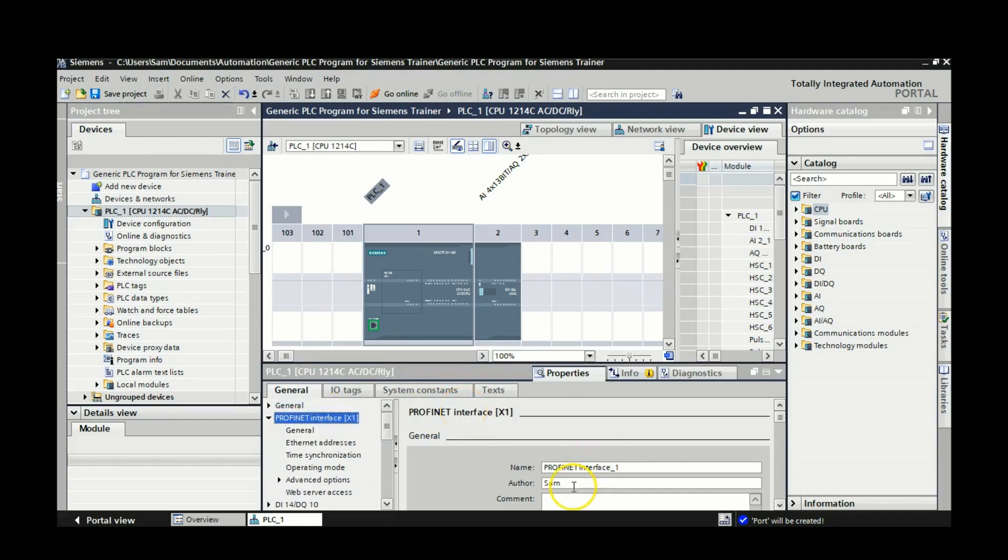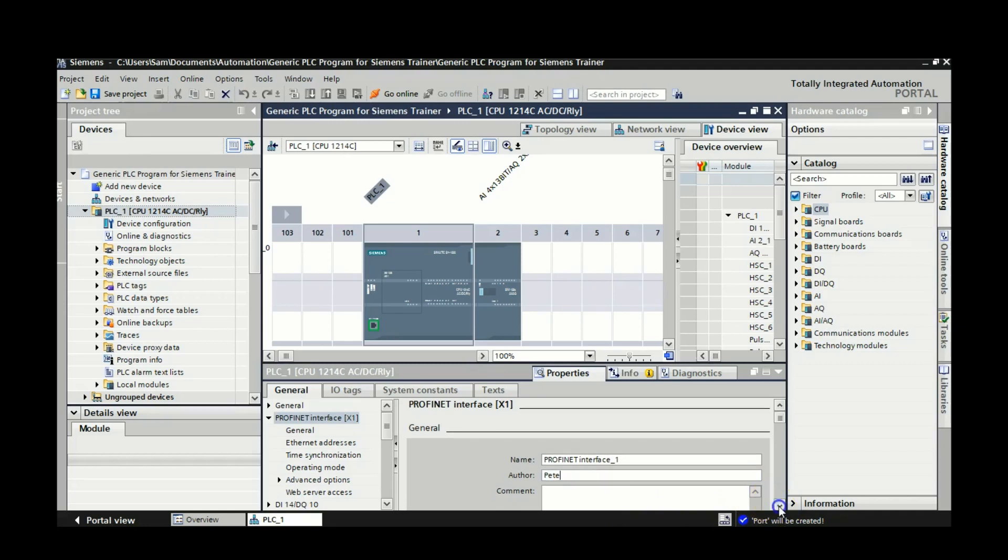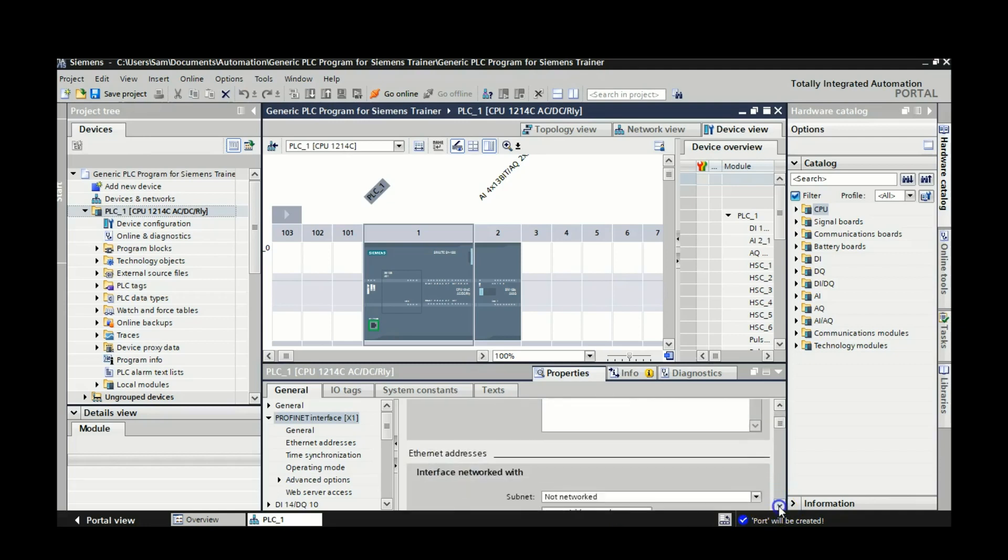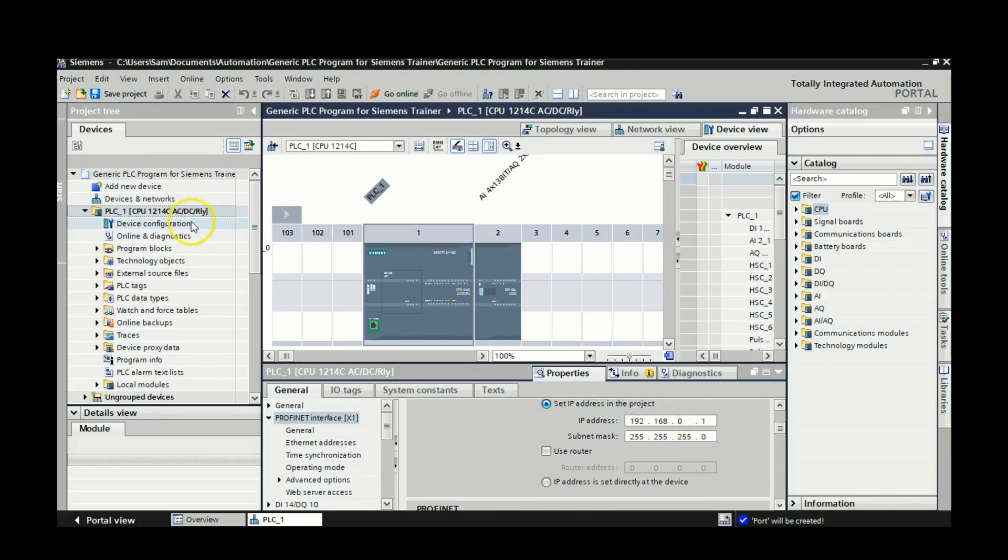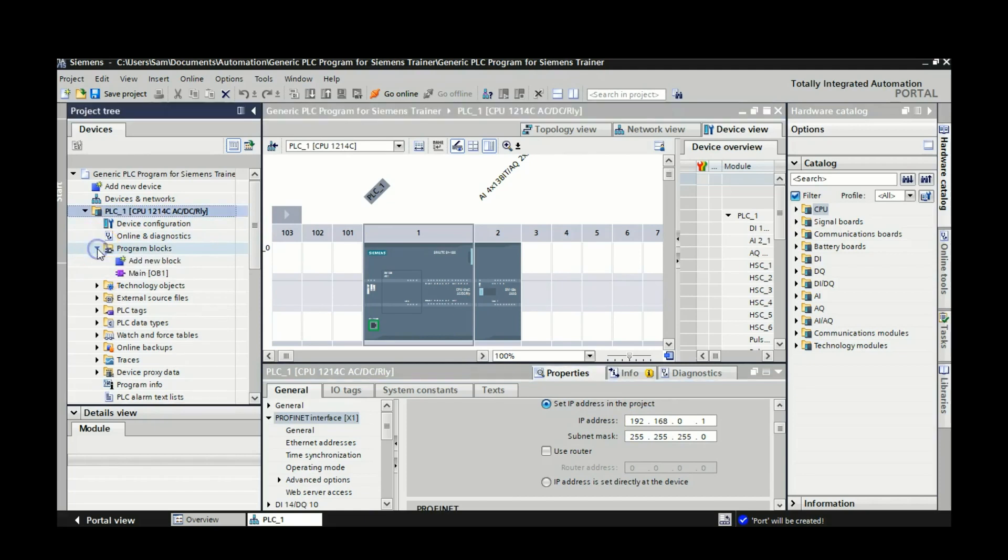So we'll go to Profinet interface. Again not sure why when I change the author it doesn't change it all the way through, but if you scroll down here on Profinet interface, there's that same IP, 192.168.0.1. That's the specific IP for my PLC. You will have a specific IP for each individual PLC in the lab.